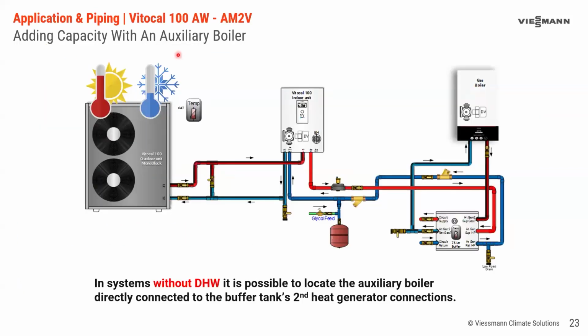So if you don't have any domestic hot water, you could put this boiler directly connected to the buffer tank. There are two tappings for second heat generator on the buffer tank, and this works perfectly fine to load the buffer tank up and maintain the heat, maybe even a little bit more accurate because we have a much shorter run of pipe here, and this is going to be maintained at whatever the boiler set point is. But it doesn't work if you have the DHW because the tank is here. When it switches to DHW, which I don't show in this drawing, there's no way for this heat to get to the buffer or to the indirect tank. So that's why we've shown it in the other position in the previous drawings. Okay.